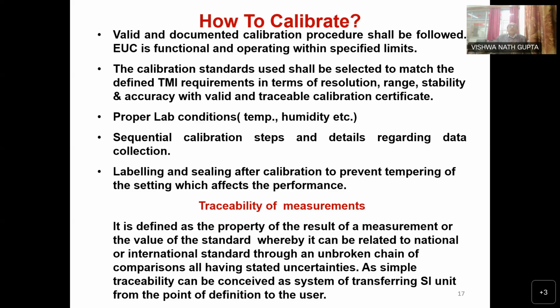So that's why, sir, uncertainty plays a vital role, and unfortunately it is not looked after by the users also. They think, okay, our instrument has been calibrated, an NABL logo is there, so that instrument can be used for working. It is giving a major problem, sir. Nobody is looking at the uncertainty, so the firms have to be very careful to see the uncertainty, whether the instrument is usable or not even after calibration.